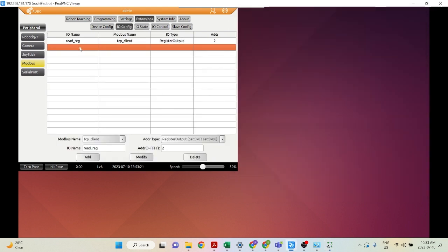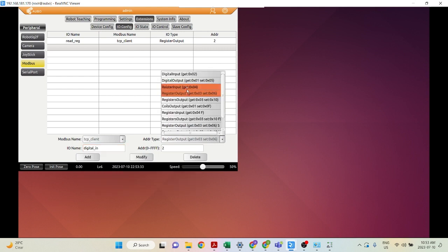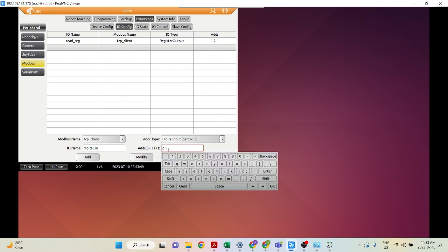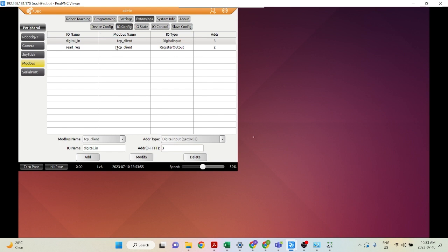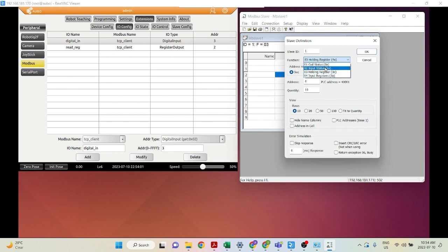You can also add other IOs. Let's add a digital input. Now we're only able to read from the slave with this type. For the address, you can set it the same as before or a different address — let's use a different one, address 3. Click Add. Now set up the slave to use Input Status, because we're using digital input as the address type.